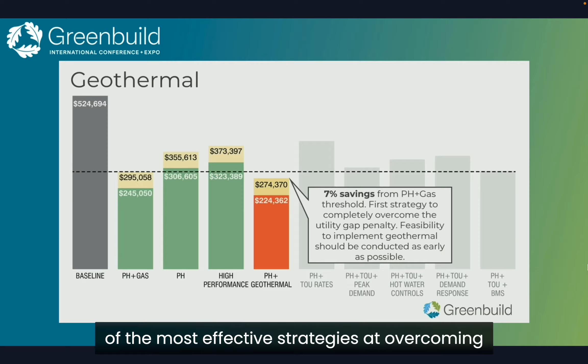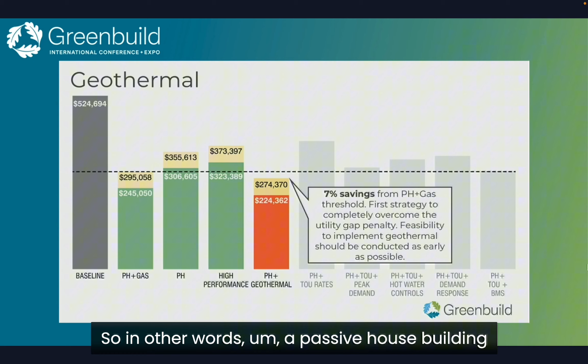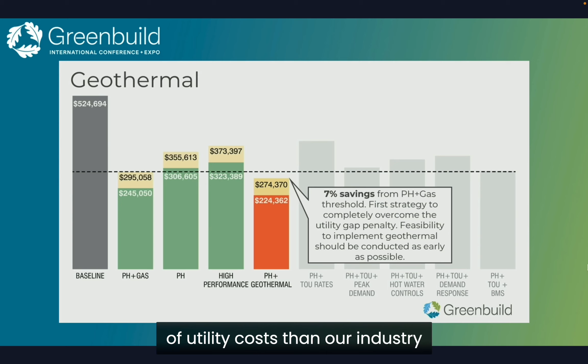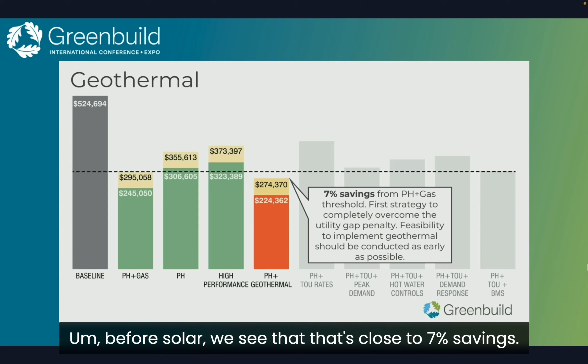The next point of comparison we looked at is passive house plus gas. This is the industry standard, where most of the building is electrified except for domestic hot water. To date, this is the most cost-effective way we've found to do mostly electrified passive house multifamily buildings. You can see a significant drop in utility costs, from about $520,000 a year to under $300,000.